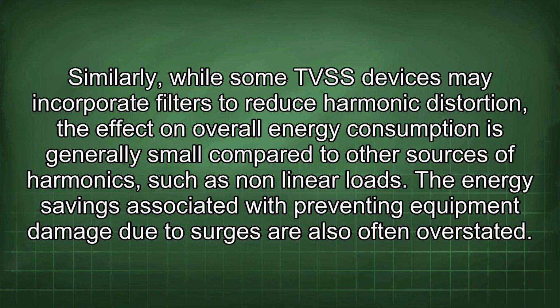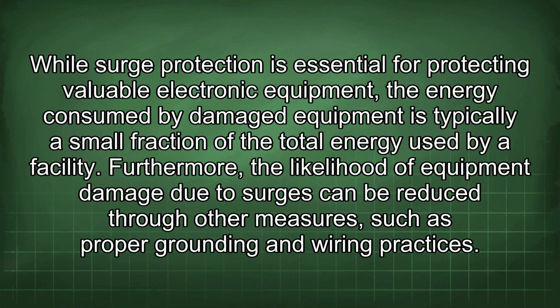Similarly, while some TVSS devices may incorporate filters to reduce harmonic distortion, the effect on overall energy consumption is generally small compared to other sources of harmonics such as nonlinear loads. The energy savings associated with preventing equipment damage due to surges are also often overstated. While surge protection is essential for protecting valuable electronic equipment, the energy consumed by damaged equipment is typically a small fraction of the total energy used by a facility.